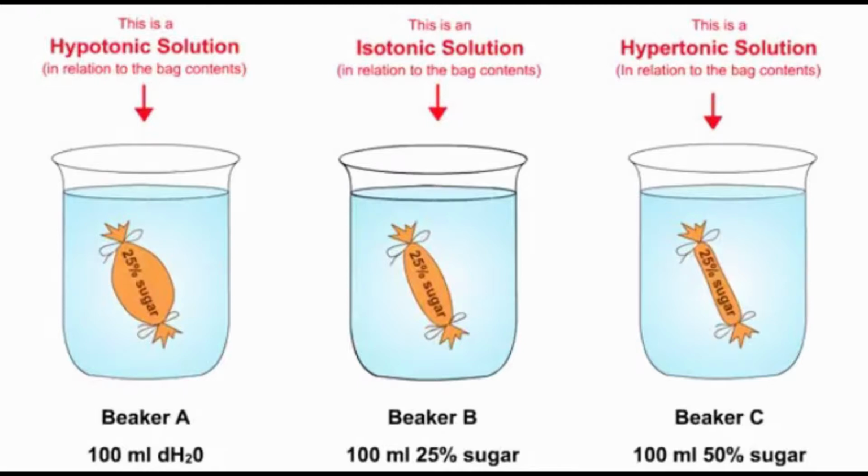Isotonic, the fluid inside the cell has the same salt concentration as the solution surrounding the cell. This condition describes regeneration steps where the TDS is the same inside of the resin bead as the solution surrounding the resin. Hypertonic, having a higher TDS concentration outside of the cell than that of the fluid inside of the cell. This condition describes the start of the brine draw step of the regeneration process.